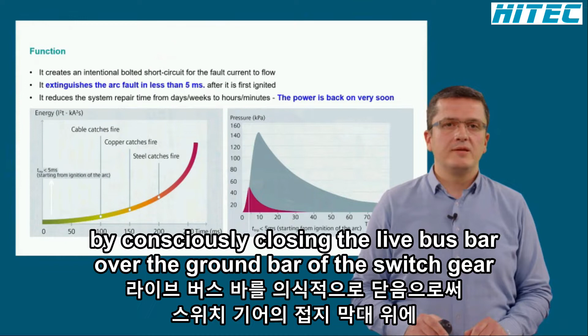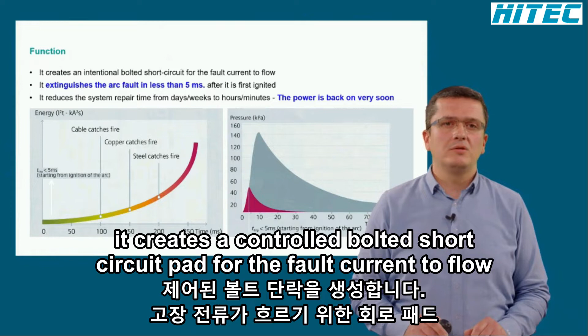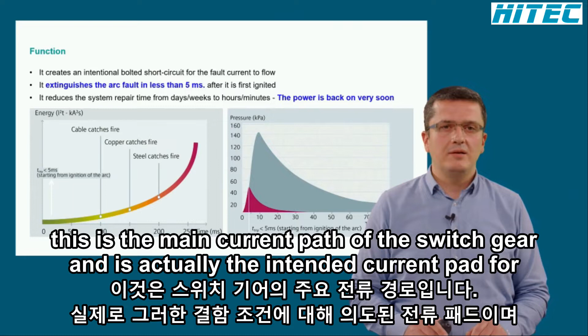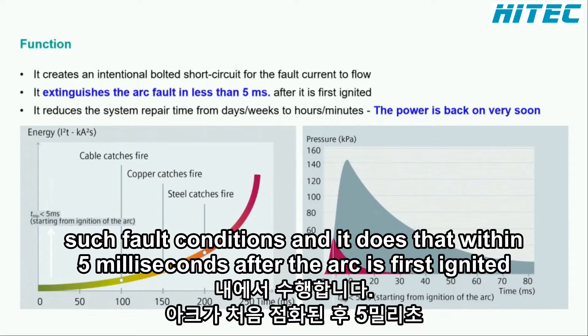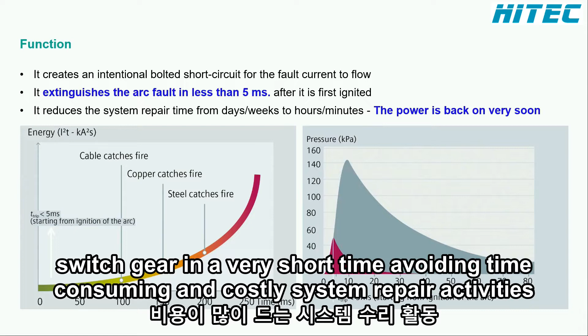So, SIQuench, in the case of an internal arc, by consciously closing the live bus bar over the ground bar of the switchgear, creates a controlled, bolted short circuit path for the fault current to flow. This is the main current path of the switchgear and is actually the intended current path for such fault conditions. And it does that within 5 milliseconds after the arc is first ignited. By doing so, it prevents the damaging effects of an arcing fault and allows to re-energize the switchgear in a very short time, avoiding time-consuming and costly system repair activities.